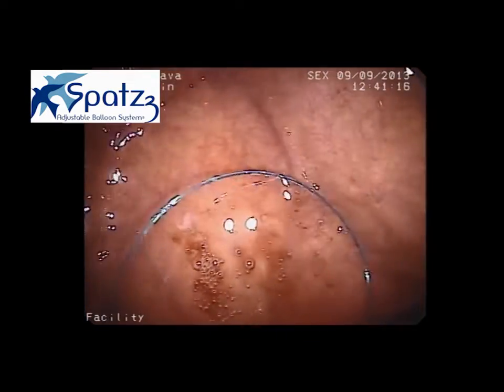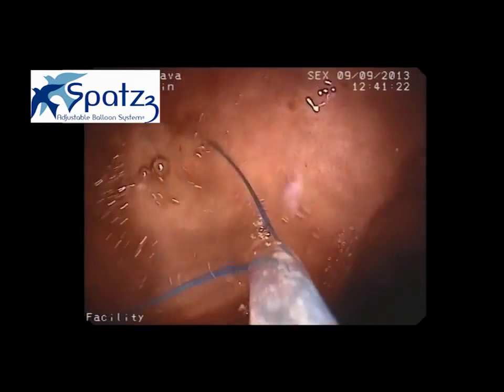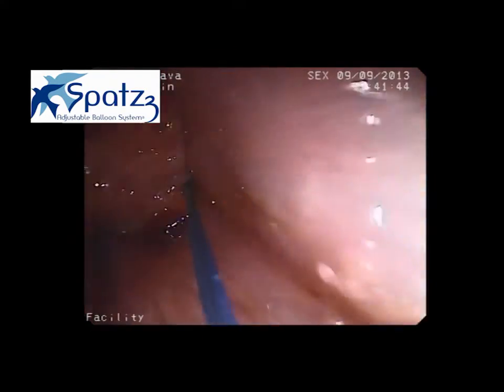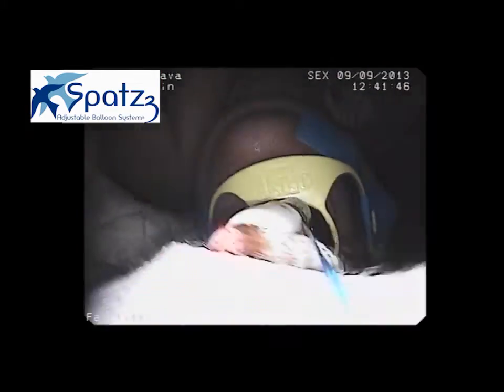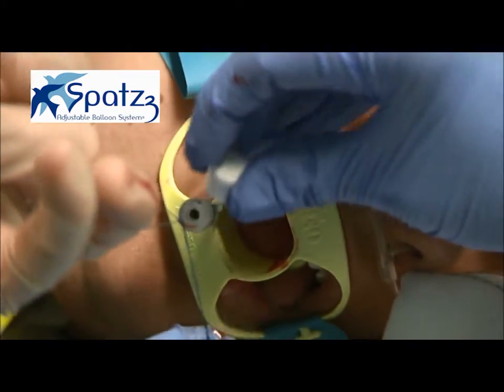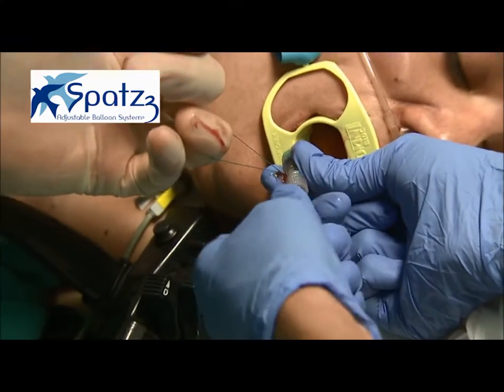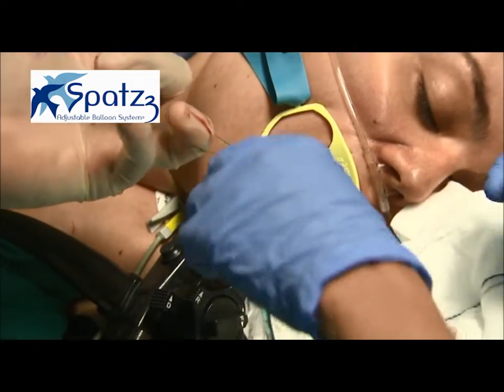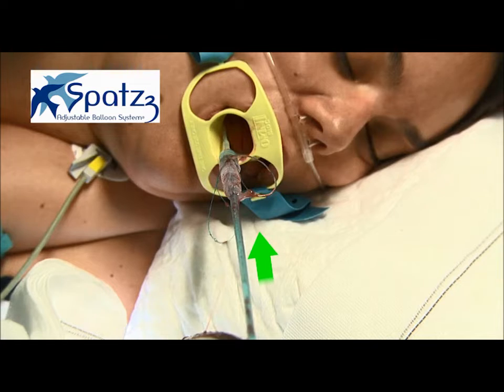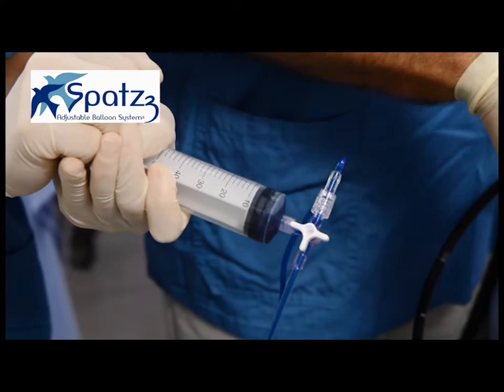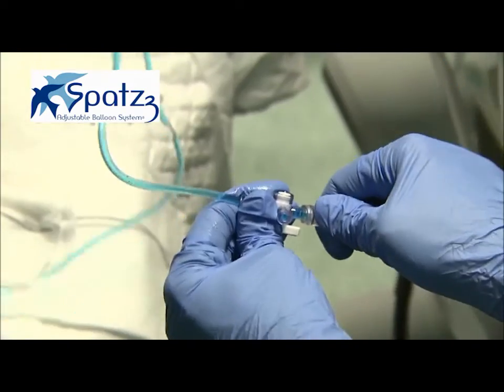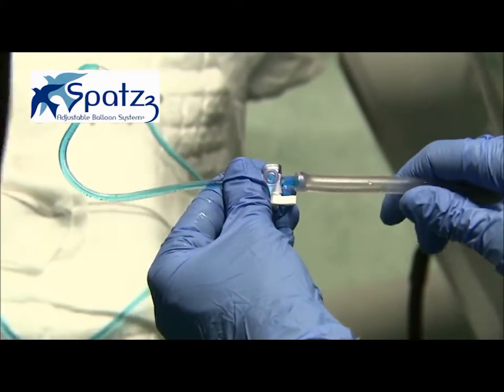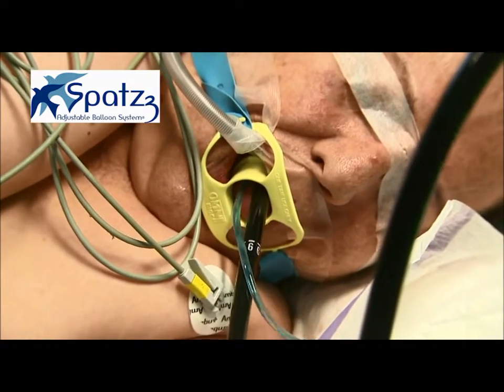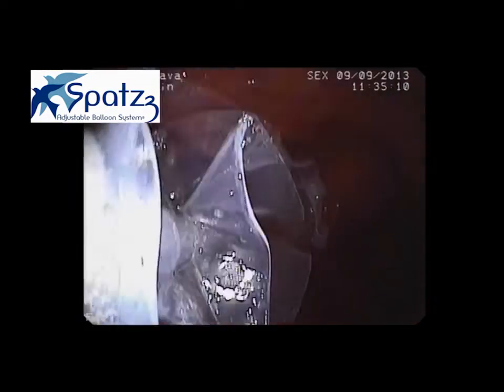The easy grasp valve is captured. The endoscope is removed with the valve pulled to the tip of the endoscope. The cap is twisted off and the valve is connected to the extension tube. The extension tube is lowered into the throat until there is no further pulling on the tube. Deflate completely manually or by connecting to the suction apparatus. Reinsert the endoscope to confirm complete deflation.